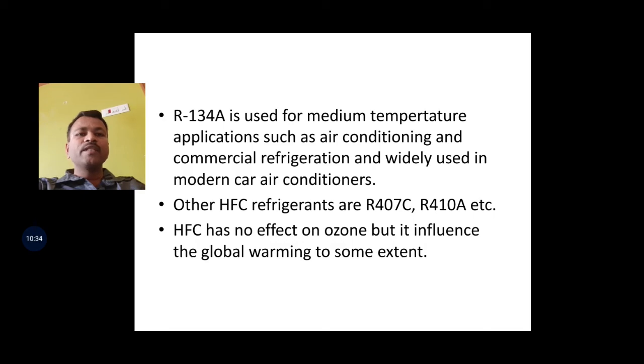Next, R134 is used for medium temperature applications such as air conditioning and commercial refrigeration, and is widely used in modern car air conditioners. Other hydrofluorocarbons are R407C, R410A, etc. You can use them as an alternative for Freon 12 and Freon 22. The hydrofluorocarbon has no effect on ozone, but it has an effect on global warming to some extent. Okay, global warming is the greenhouse effect. So again, that is why the researchers are working on this, to find the best refrigerant for the refrigeration process.